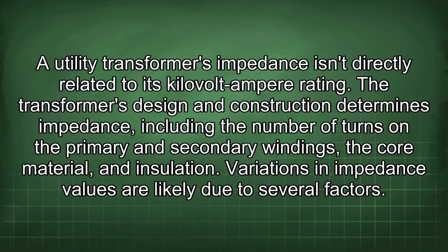A utility transformer's impedance isn't directly related to its kilovolt-ampere rating. The transformer's design and construction determines impedance, including the number of turns on the primary and secondary windings, the core material, and insulation. Variations in impedance values are likely due to several factors.